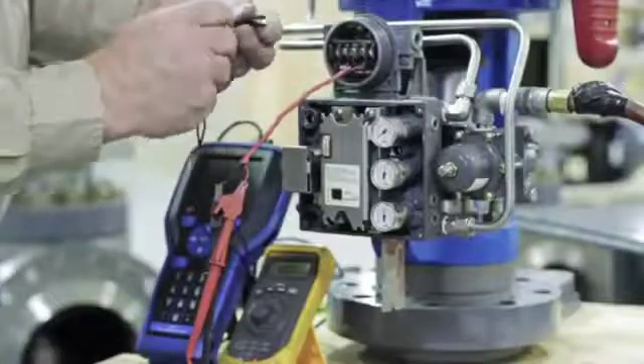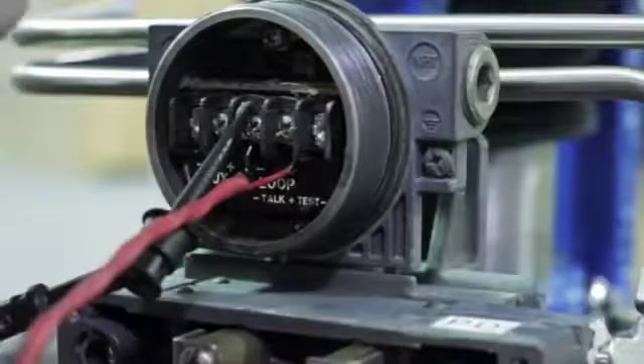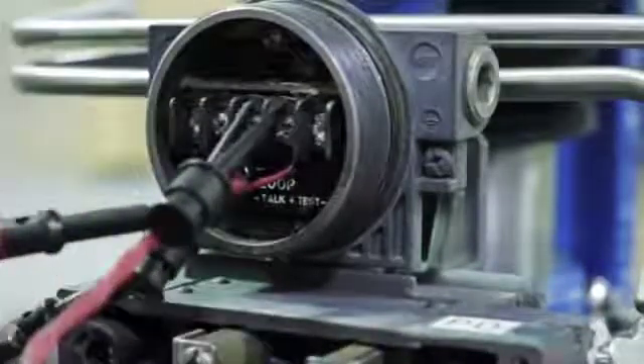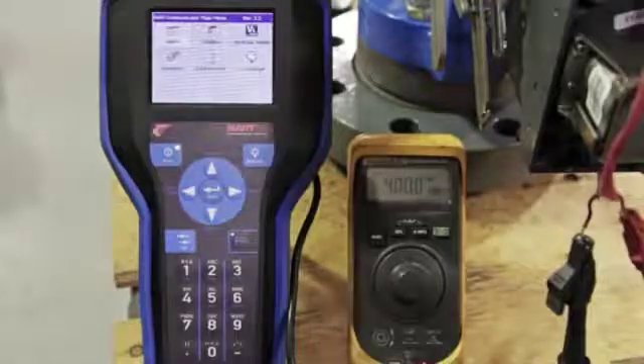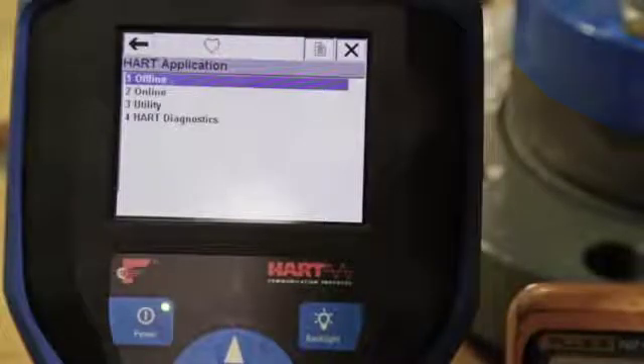Connect the 475 field communicator to the terminal box loop terminals as well. The beating heart graphic on the 475 handheld lets you know that communication has been established with the positioner. On the 475 startup screen, select HART.